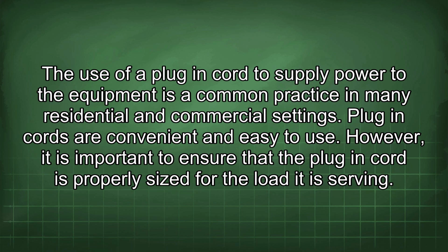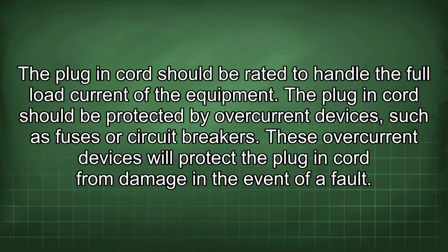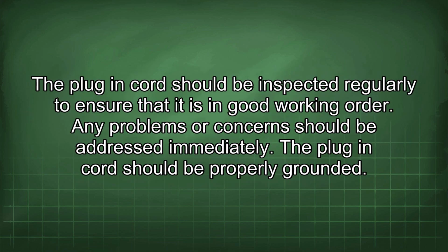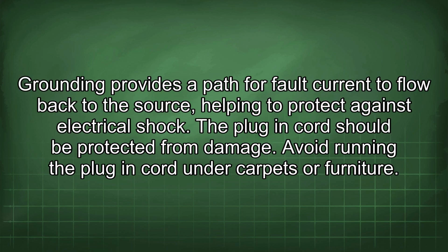However, it is important to ensure that the plug-in cord is properly sized for the load it is serving. The plug-in cord should be rated to handle the full load current of the equipment. The plug-in cord should be protected by overcurrent devices, such as fuses or circuit breakers. These overcurrent devices will protect the plug-in cord from damage in the event of a fault. The plug-in cord should be inspected regularly to ensure that it is in good working order. Any problems or concerns should be addressed immediately. The plug-in cord should be properly grounded. Grounding provides a path for fault current to flow back to the source, helping to protect against electrical shock.